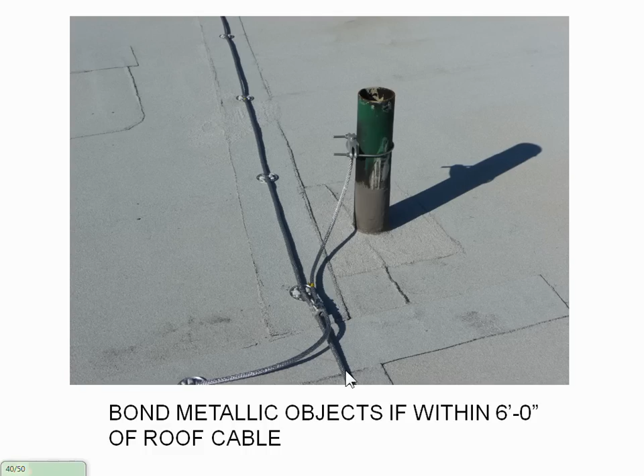This is another big thing. Any metal object that's on the building and within 6 feet of the cable needs to be tied to the system. The reason for that is 6 feet is the magic number. If lightning is traveling through this conductor, any metallic object within 6 feet actually risks having a side flash. If you don't equalize the potential between the two, basically it'll side flash here, decide to use this as the downlink to ground, and then go throughout your building and wreak havoc. So what that does is tie the two together.